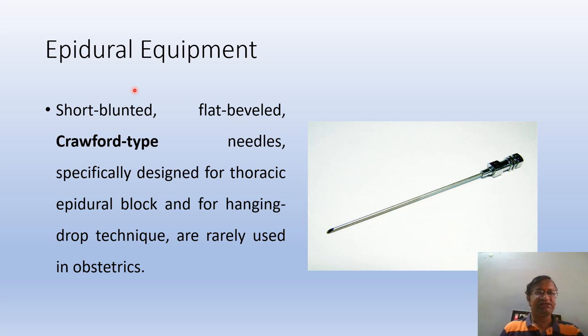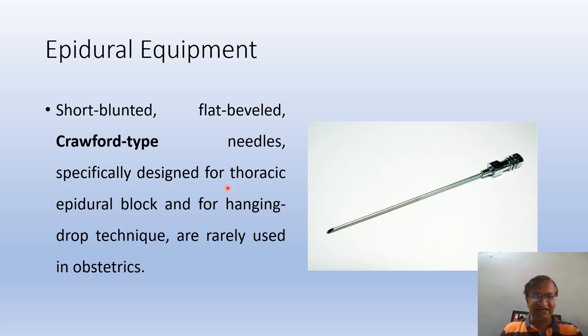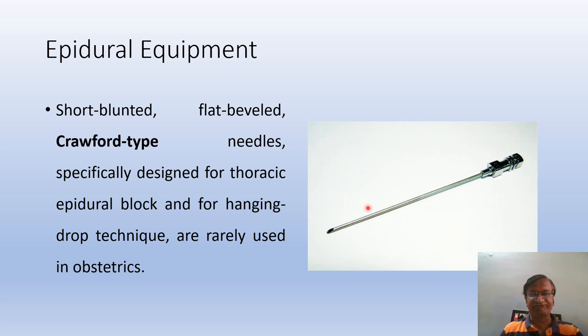This is a short, blunted, flat-bevel Crawford-type needle. It is specifically designed for thoracic epidural block and for the hanging drop Crawford technique, and it is not used in obstetrics. As you can see, this is the Crawford type — flat bevel, short blunting.